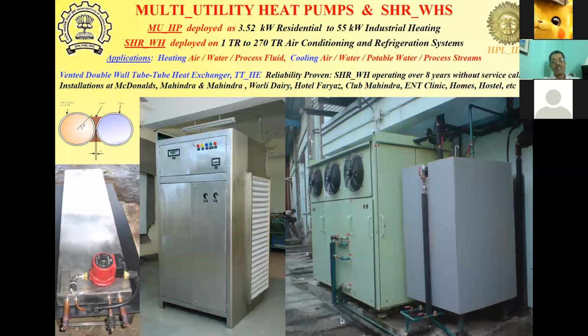So in this particular form, which you see here, this is a compact unit with just a 1 meter by 1 meter footprint, and it can give you cooling as much as 12 tons. This particular unit is an 8.3 ton capacity unit, but a 12 ton compressor can be incorporated in the same size, or we have given 12 ton compressors also in the same footprint with the evaporator extending all the way to the top on either side of the heat exchanger. Right now it's extending only up to this. So ambient air, or the surrounding air, gets filtered, cooled, dehumidified, heat is extracted by the evaporator from this, and then the heat plus the compressor power required to compress the refrigerant from the low vapor pressure from the evaporator to the condenser pressure is then delivered out in the condenser.